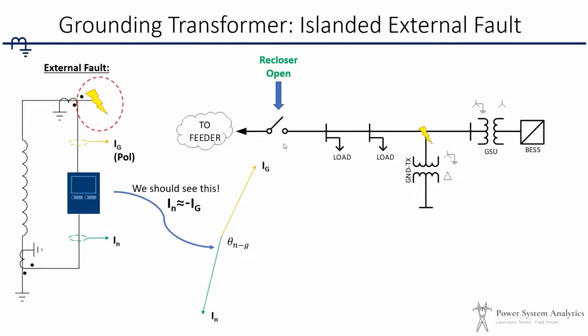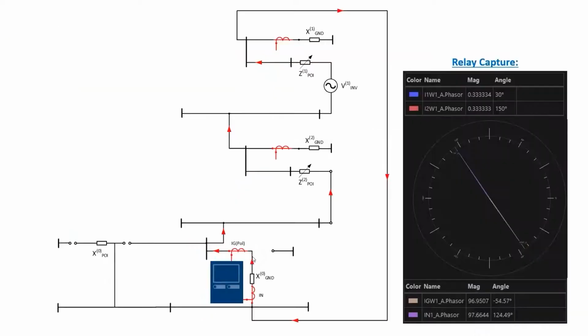All right, well, without further ado, we're going to island it. So we went through the process of actually opening the switch, the recloser, and placing an external fault in the network, and then taking a look at what we had there. As you slide the fault inside the microgrid, which is exactly what we were doing, we expect to see this phasor quantity, something similar to what we were seeing before with it grid tied, which is exactly what happened.